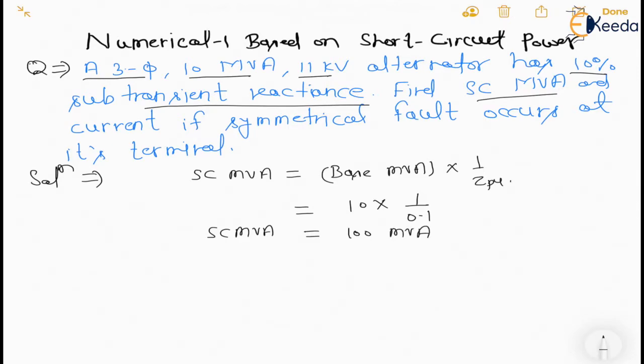And now we need to calculate short circuit current. So first we will find out the base current. We know in case of three phase, IB is equal to MVA into 1000 upon root 3 into KVB.